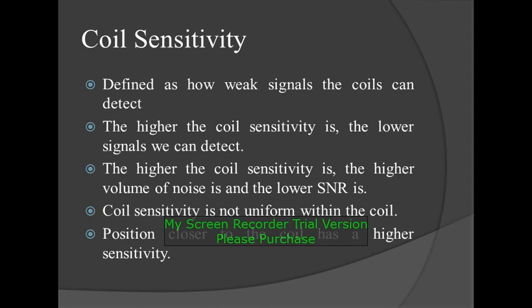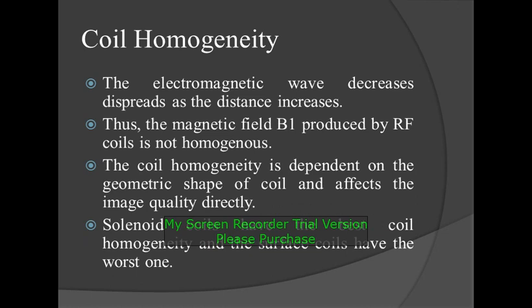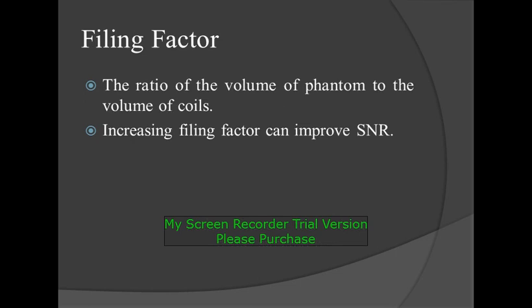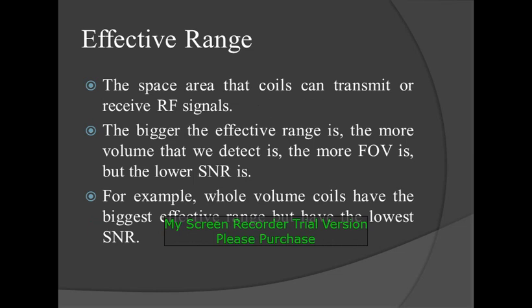Coil homogeneity: electromagnetic waves decrease and spread as the distance increases. Thus, the magnetic field B1 produced by an RF coil is not homogeneous. Coil homogeneity is dependent on the geometric shape of the coil and affects image quality directly. Solenoid coils have the best coil homogeneity and surface coils have the worst. Filling factor: the ratio of the volume of phantom to the volume of the coil. Increasing the filling factor can improve SNR. Effective range: the space area that coils can transmit or receive RF signals. The bigger the effective range, the more volume detected and the larger the FOV, but the lower the SNR. Whole volume coils have the biggest effective range but the lowest SNR.